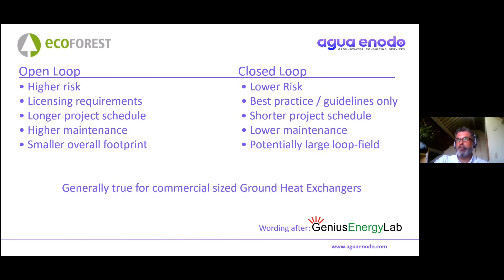So for a heating-only system looking at closed loop, we obviously have to have fairly careful regard to what the ground temperatures are going to be. Whereas with an open loop, depending on the ambient groundwater temperature, we might get an opportunity to start and continue abstracting at a stable ambient temperature, giving us a better opportunity for a smaller, more efficient system. Whereas if we have a very well balanced system, then with closed loop we also have an opportunity to make that a smaller, more efficient system. So, the most efficient - it depends.